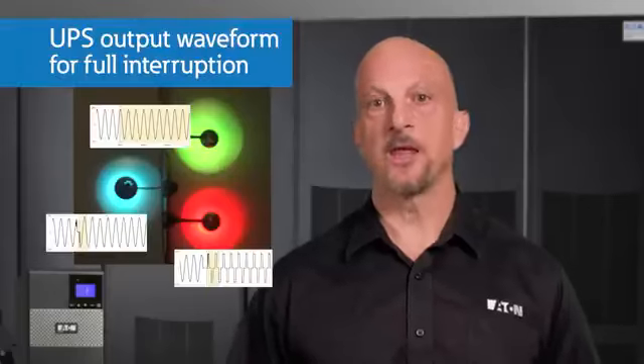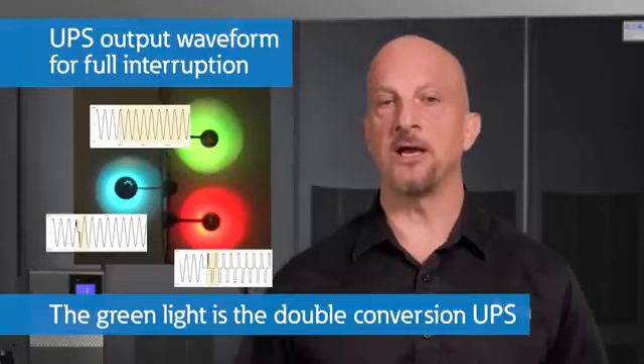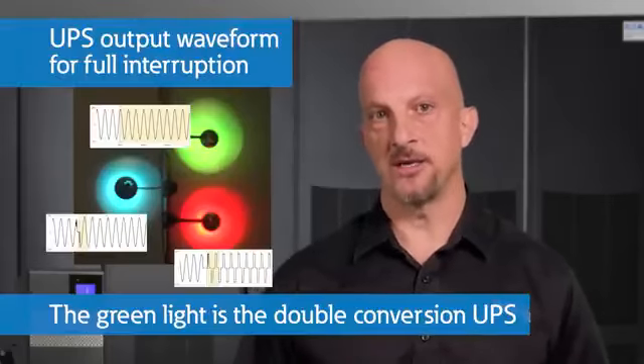When the source voltage goes away and comes back 2 seconds later, watch how 2 of the lights flicker and 1 remains solid. The solid one is the online or double conversion UPS. The other 2 also flicker when they return back from the battery to normal operation.